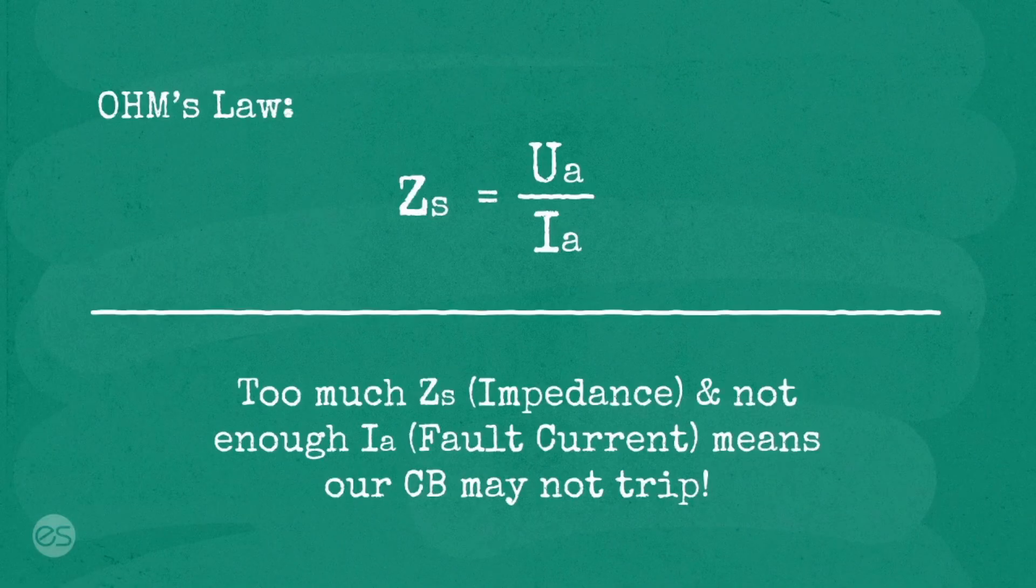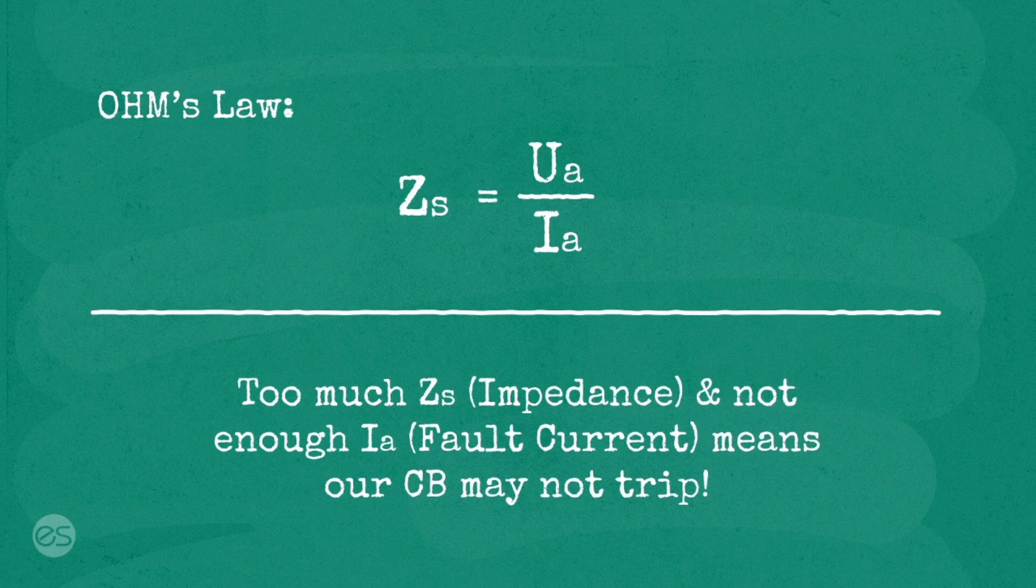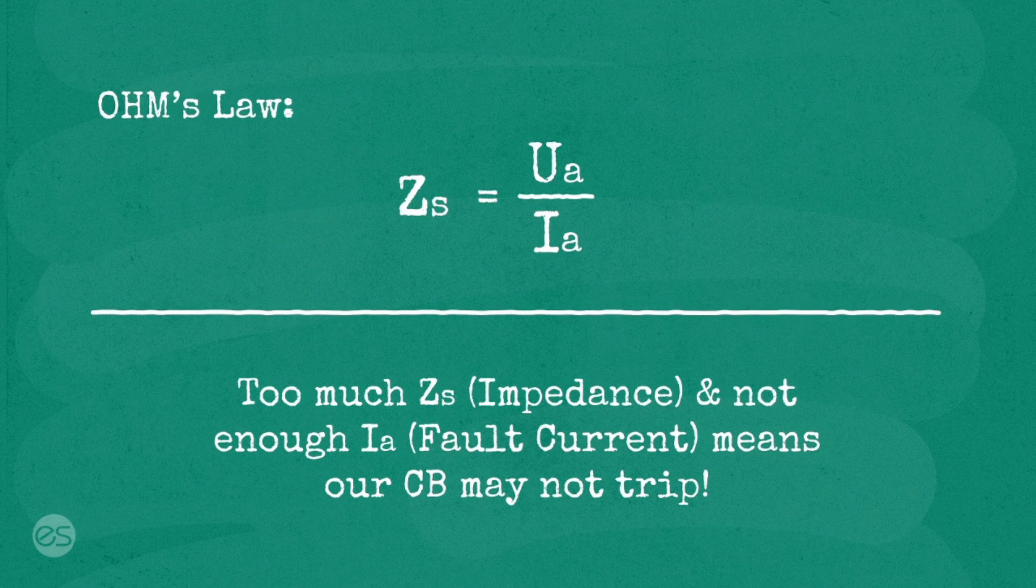Too much Zs, impedance, means not enough Ia, fault current, which means our circuit breaker can't trip or won't trip quick enough to save lives.